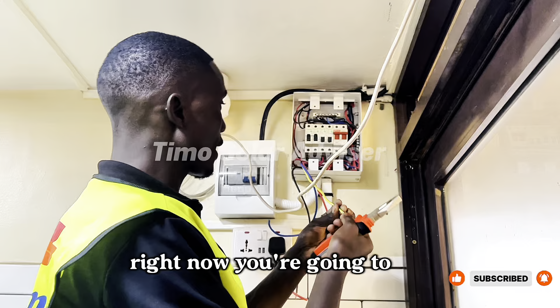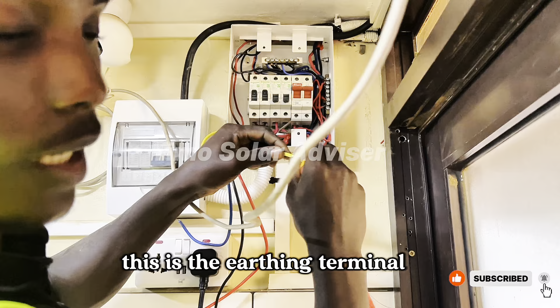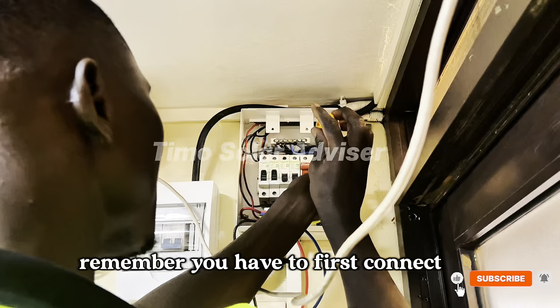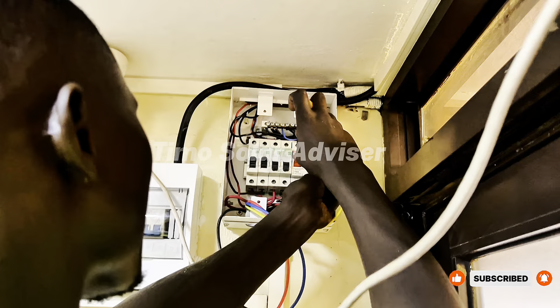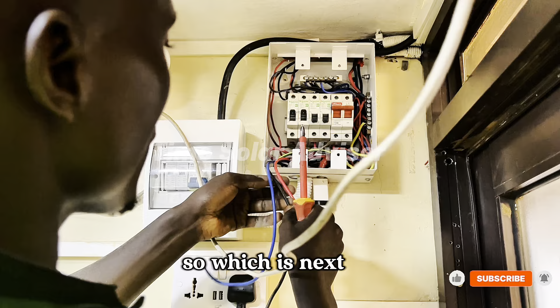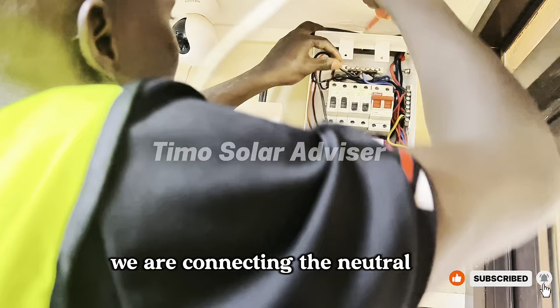Right now, we are going to first connect the earthing to the earthing point. So this is the earthing terminal. Remember, you have to first connect the earth, so that every connection is earthed and you don't get any shock. So the earthing is done. Every termination is earthed. Which is next? We are connecting the neutral. Everything is very firm.